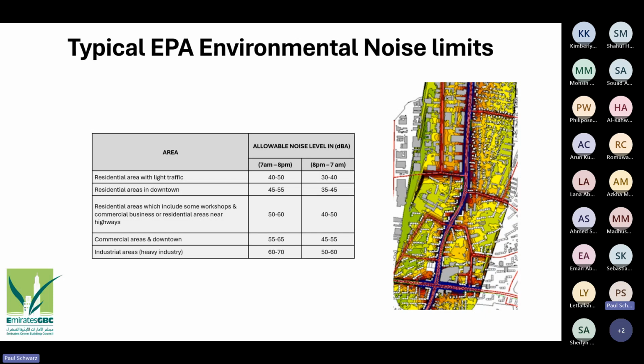But there's a common mistake that is made. A lot of consultants and developments within the GCC will look at this table, of which there are various iterations, and assume these are the noise levels recommended for a development in terms of the noise level in the general space. That's actually a common misconception. These tables, and this one specifically, relate to the allowable amount of noise that a building can contribute to the environment—it is not an indication of the noise level that affects a building.